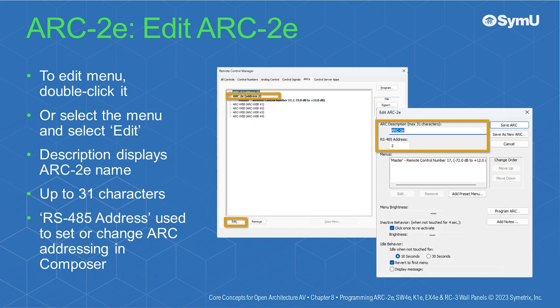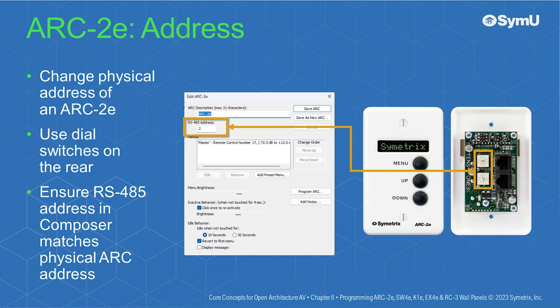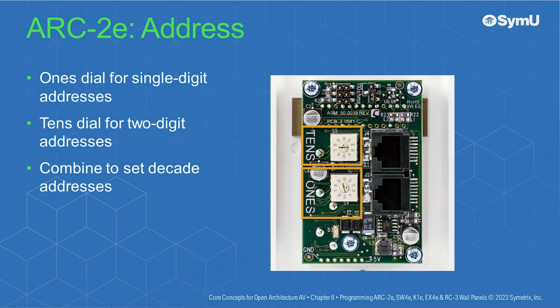To edit a menu, double-click the desired menu, or select the menu and click the Edit button. Arc Description displays the Arc2E name and can be edited with up to 31 characters. The RS485 address is used to set or change the Arc addressing in Composer. To change the physical address of an Arc2E, use the dial switches on the rear. The 1s dial changes single-digit addresses such as 1, 2, 6, 9, etc., while the 10s dial changes two-digit addresses like 10, 20, 60, 90. These dials combine to create mid-decade addresses; for example, address 25 places the 10s dial at 2 and the 1s dial at 5.